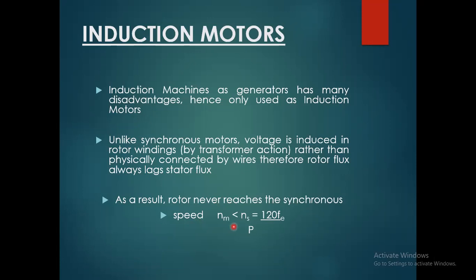We are talking about the synchronous speed. Motor mechanical speed is always less than the synchronous speed, and the synchronous speed is equal to 120 times the electrical frequency divided by the number of poles. Poles are placed on this side, the denominator.